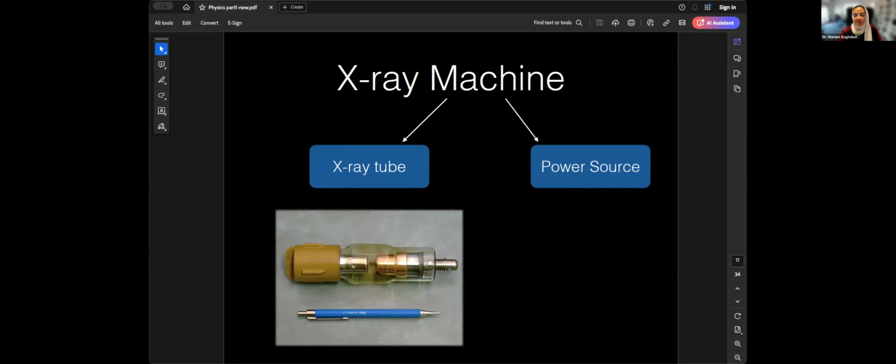The X-ray tube is seen in every single X-ray machine, whether that is an intraoral machine, a panoramic machine, or a chest X-ray machine, it doesn't matter. Every single X-ray machine has an X-ray tube. And the X-ray tube is basically where we form photons, or where we form X-ray radiation. Okay, this is where all of that happens. And we'll talk about it in detail in a second.